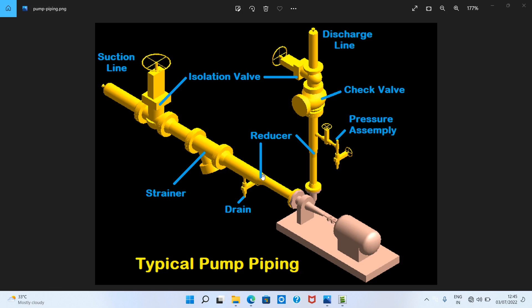Now we come to the reducer. We use an eccentric reducer in suction piping, and the reducer will be installed with the flat side up — this is to avoid cavitation and not to damage the pump.